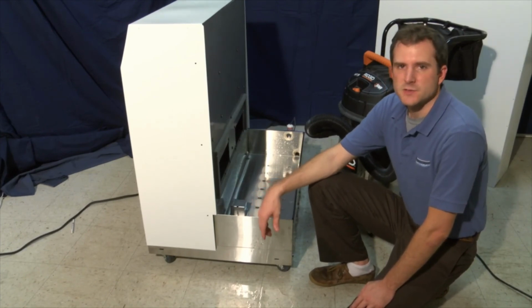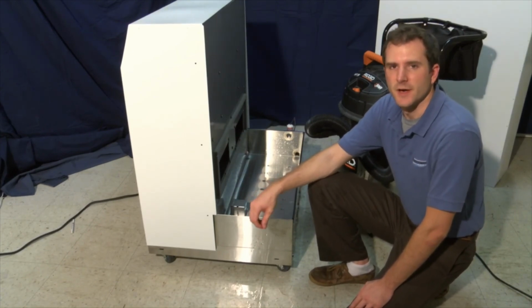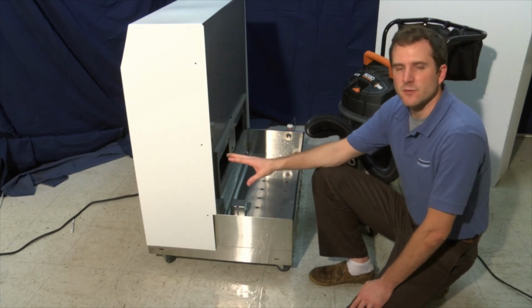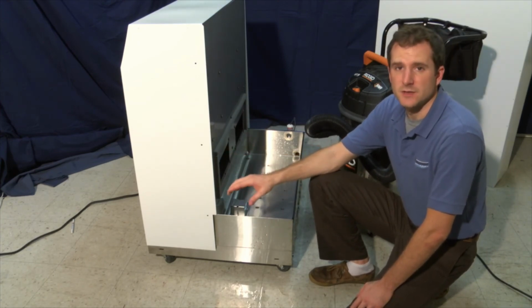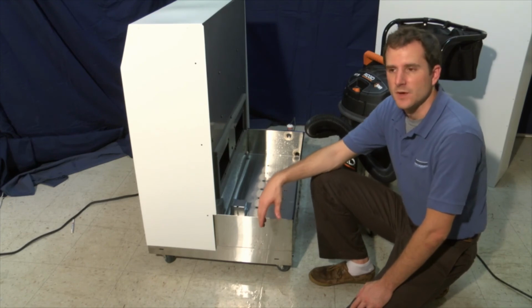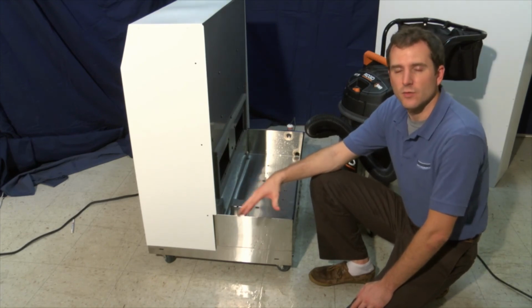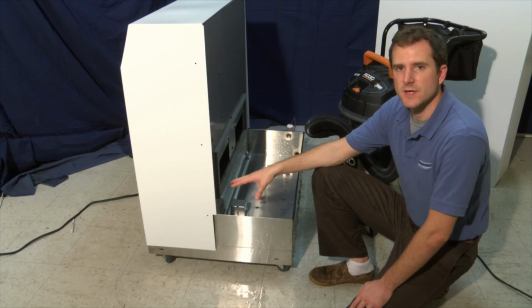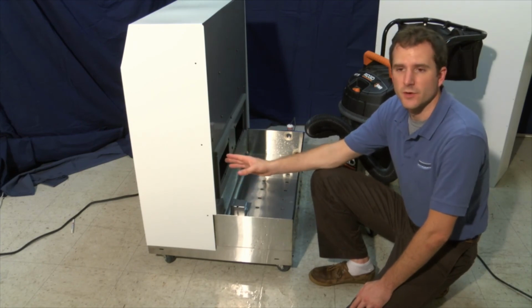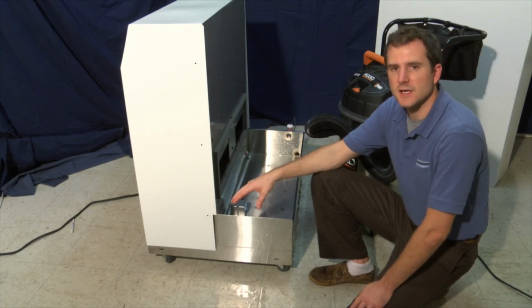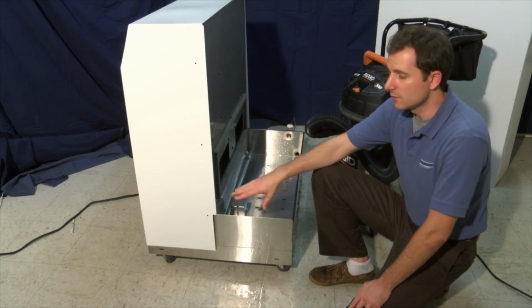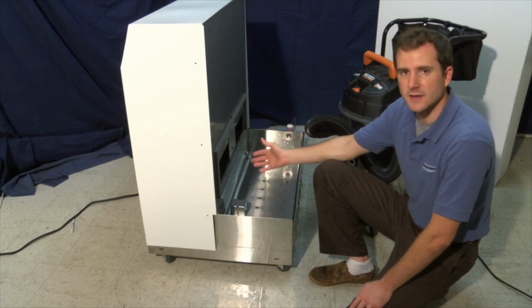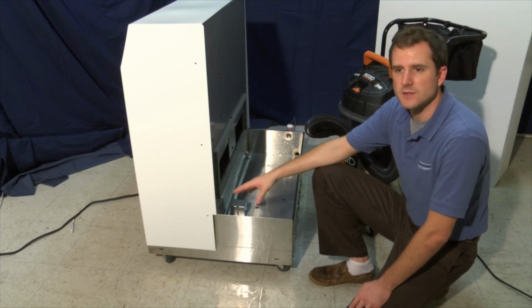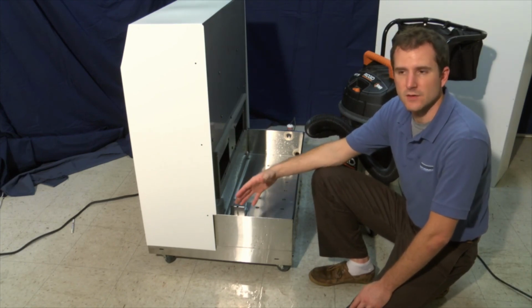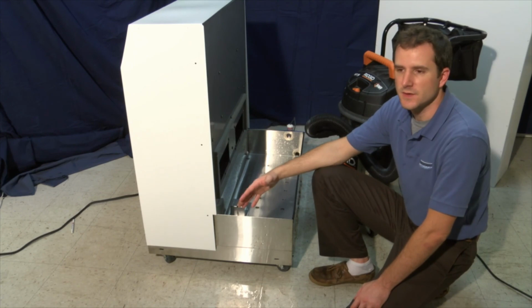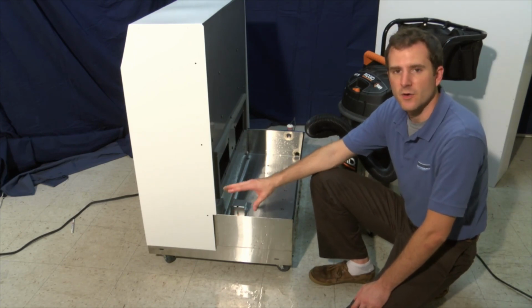The last best practice we want to talk about is seasonal shutdown. A humidifier should never be kept with water inside not being used for an extended amount of time. Stagnant water can create an organic growth or buildup that can damage the transducers or clog the solenoid. Anytime a humidifier is not going to be used for an extended amount of time, you're going to want to empty the water with a shop vac like we discussed before, and wipe the unit down with a diluted alcohol or bleach to sterilize any organic growth in there. You can then safely store the humidifier off.